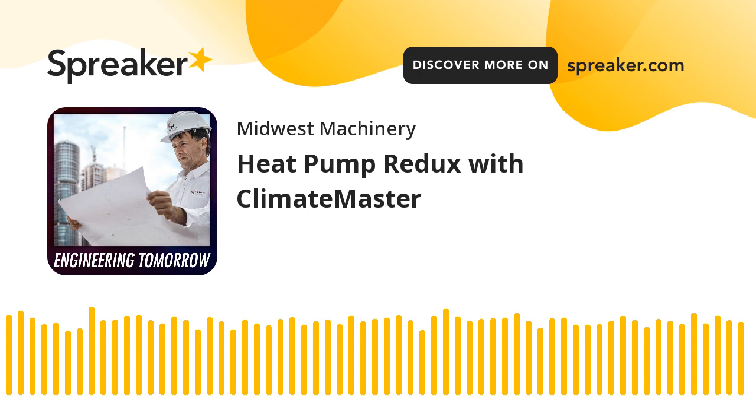All right, so moving on. Up until now, we've covered the traditional closed loop water source heat pump with a tower and a boiler, acting as our heat rejector and our heat source respectively. However, some water source heat pump systems can be provided as a towerless or a boilerless system. How do I do this? Well, these systems utilize the Earth's natural thermal properties to maintain the system loop water temp in the operating range. Remember, I keep saying 60 to 90.